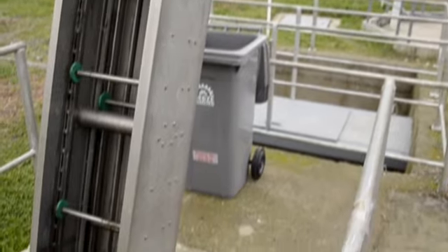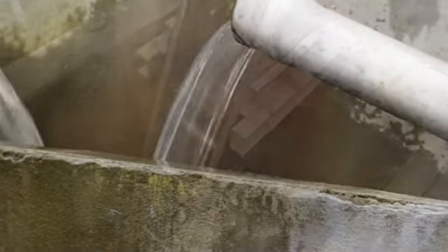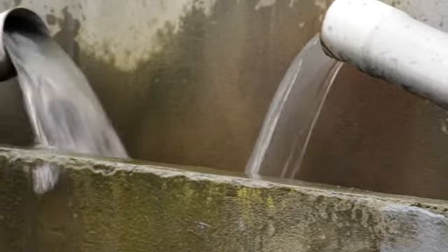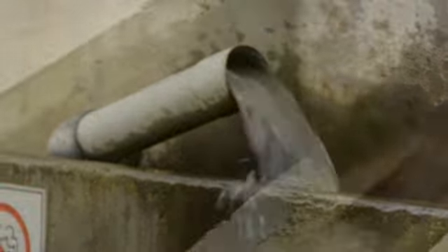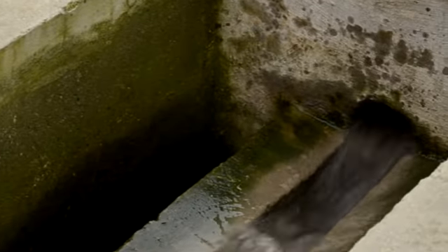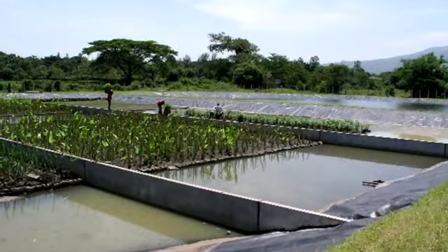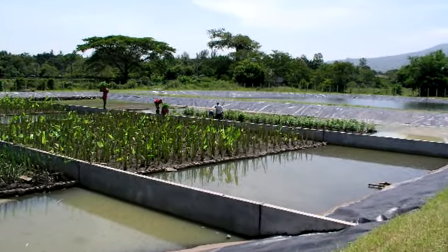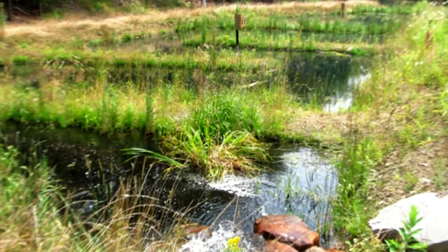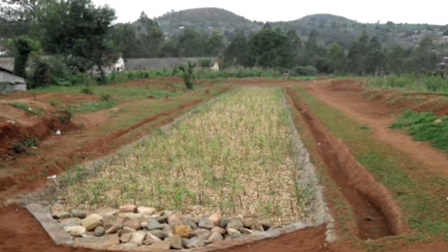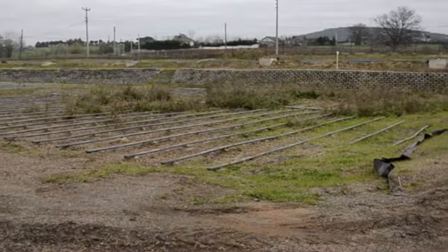Constructed wetlands are artificial wastewater treatment systems consisting of shallow ponds or channels which have been planted with aquatic plants and which rely upon natural microbial, biological, physical, and chemical processes to treat wastewater. They typically have impervious clay or synthetic liners and engineered structures to control the flow direction, liquid detention time, and water level. Depending on the type of system, they may or may not contain an inert porous media such as rock, gravel, or sand.